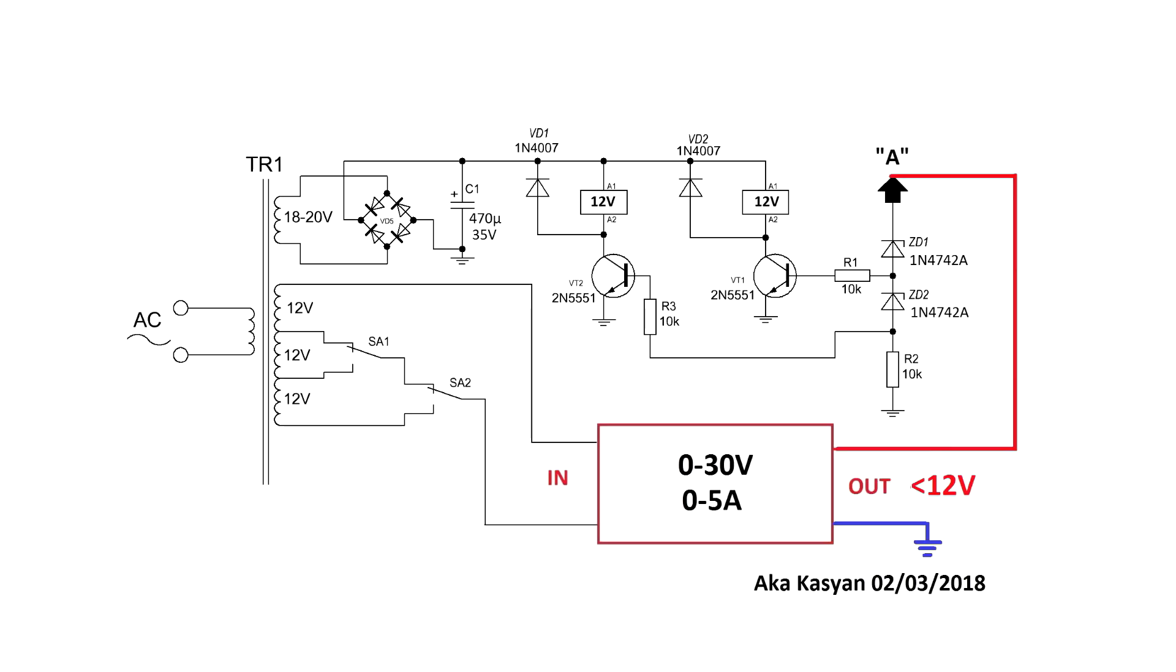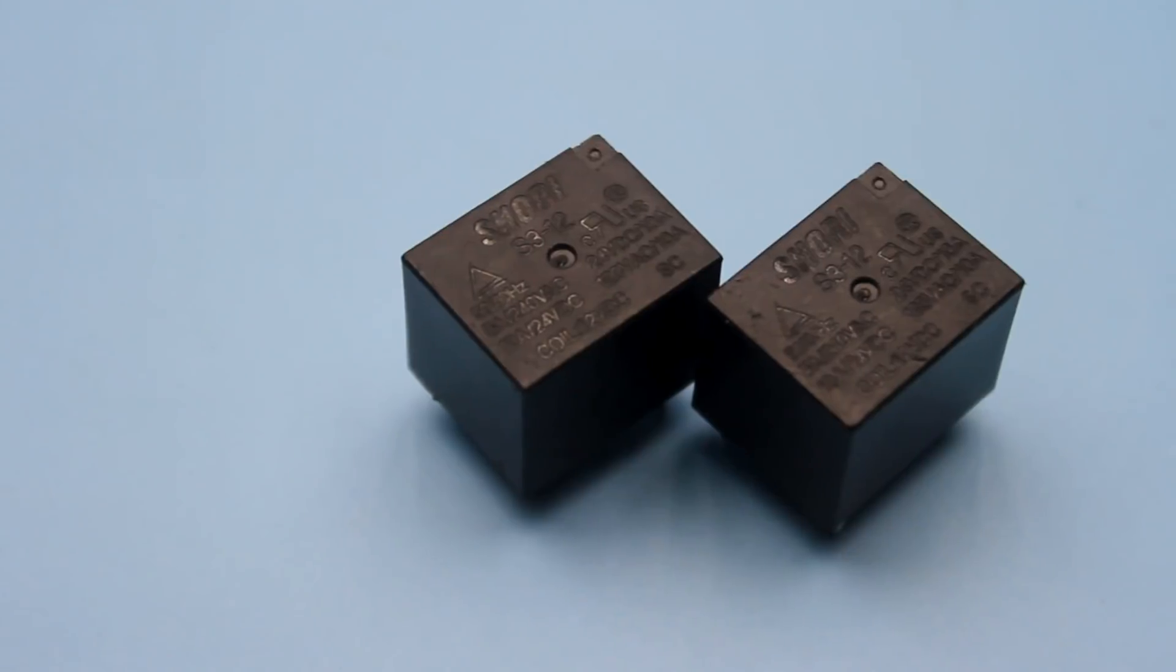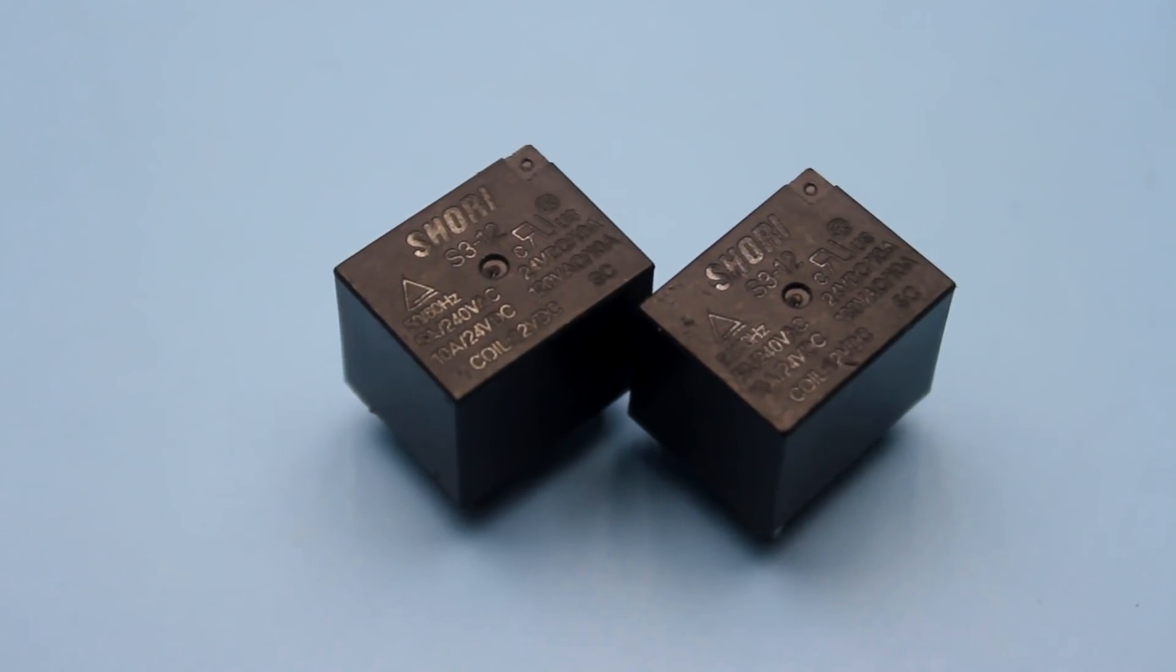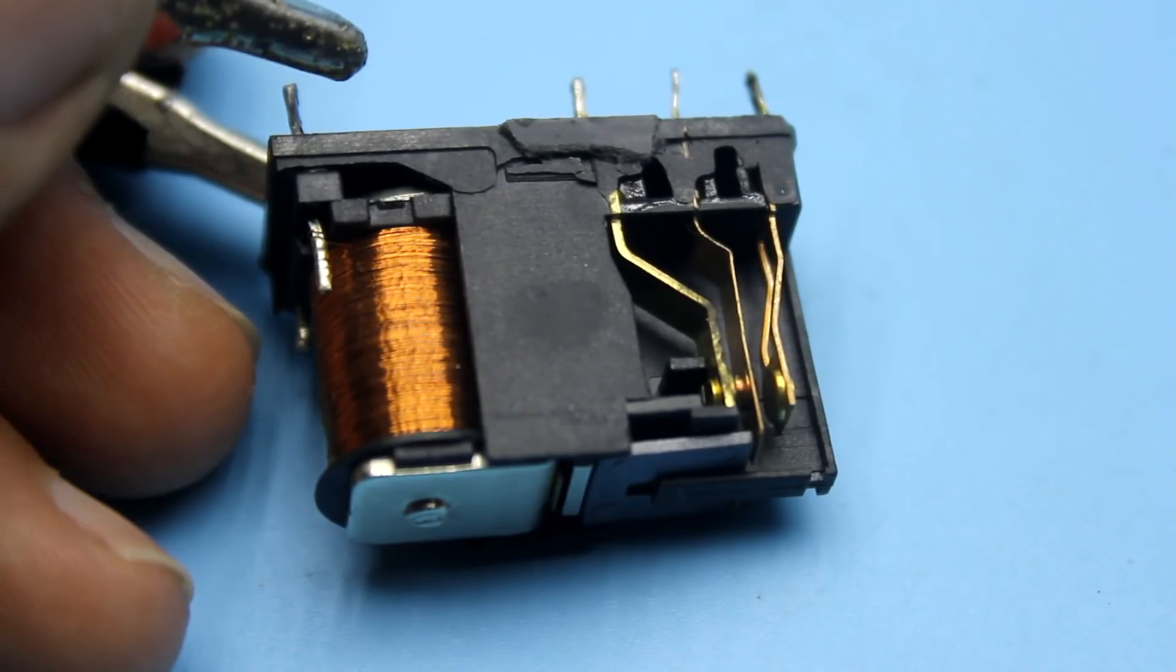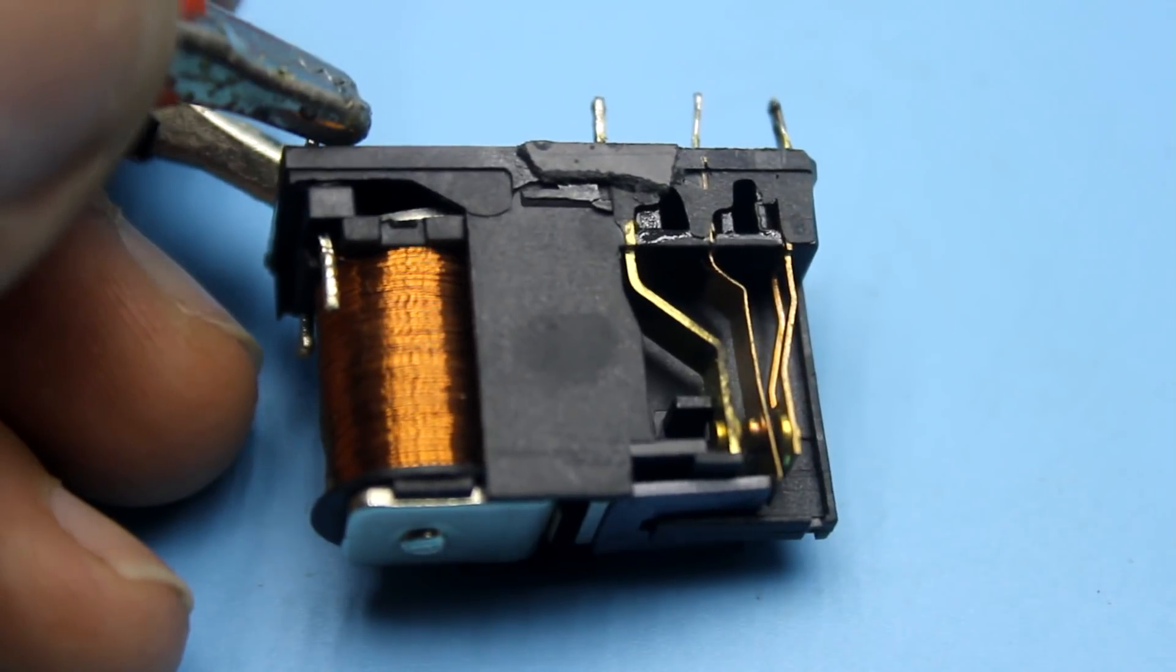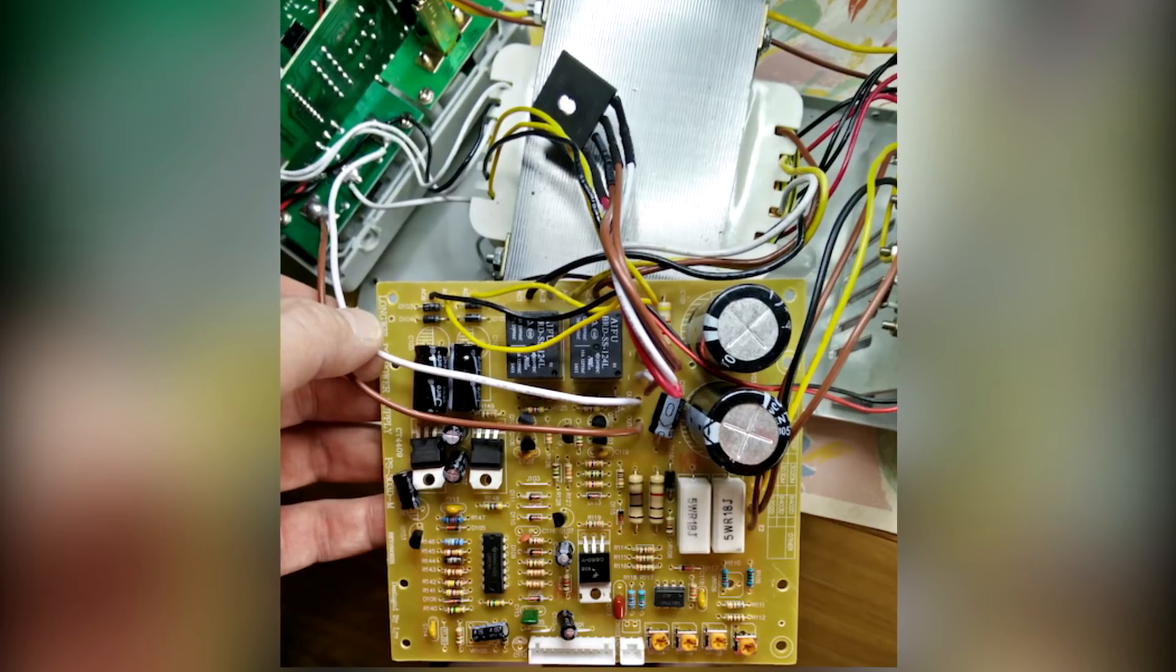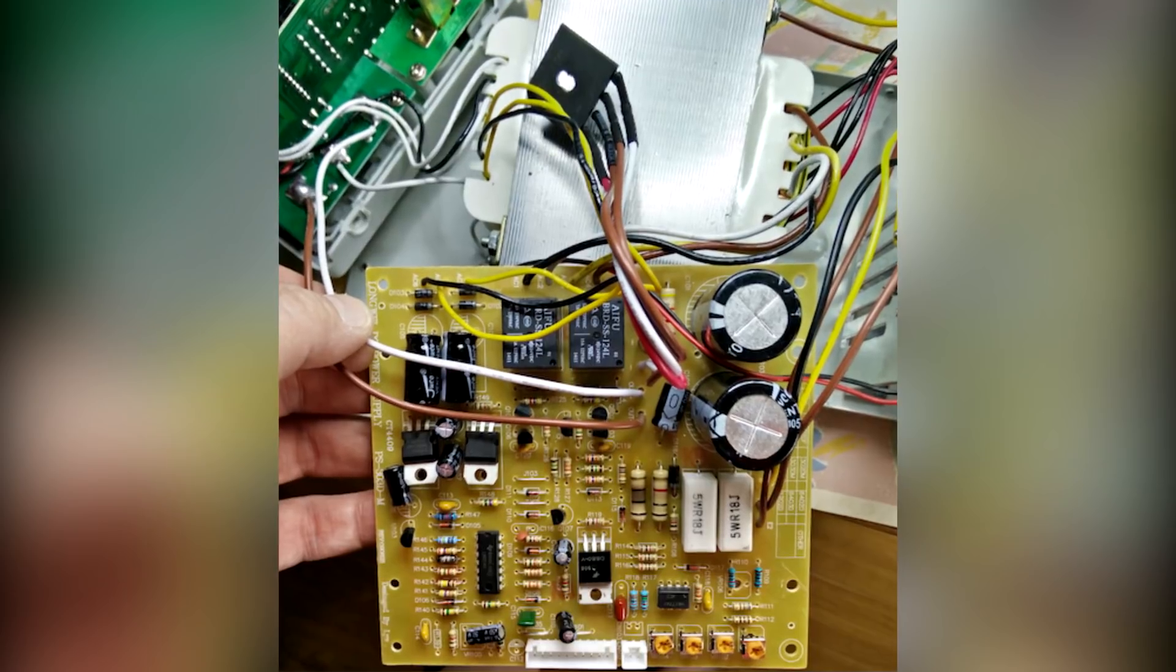Among the drawbacks of the circuit is the usage of an electromagnetic relay. The relay makes much sound during switching, and the contacts aren't eternal. But I must say that in many industrial power units just this solution is realized.